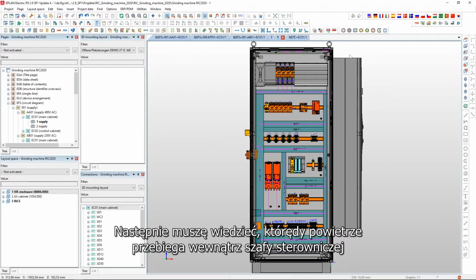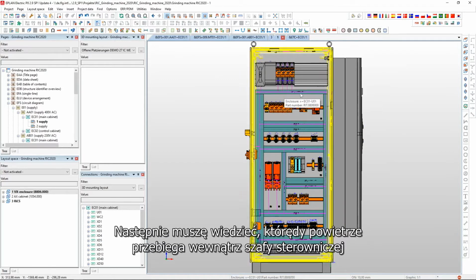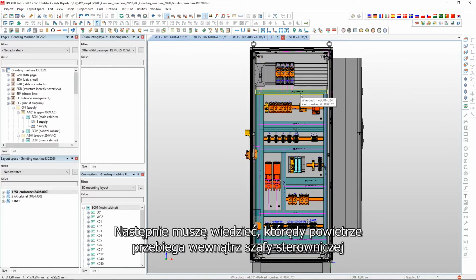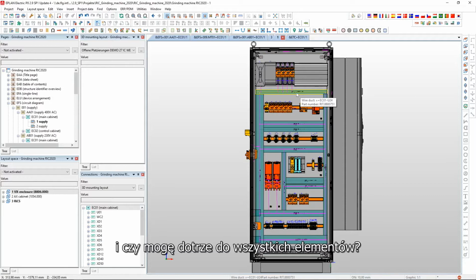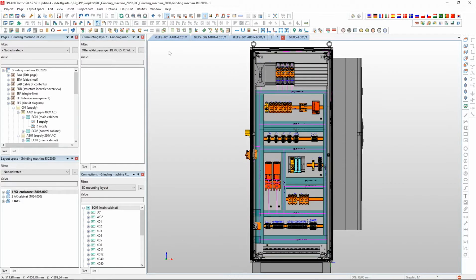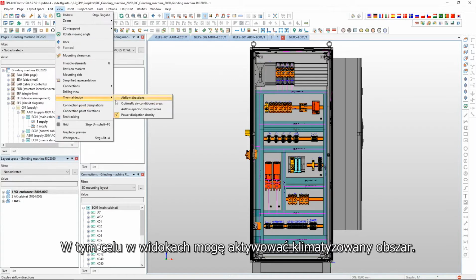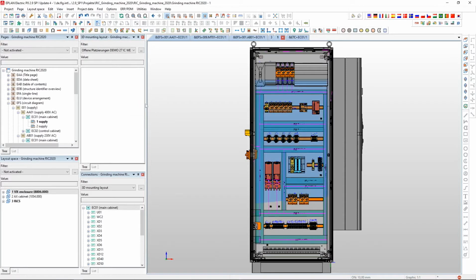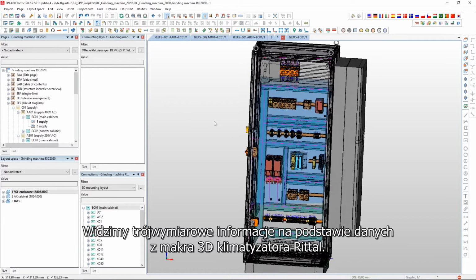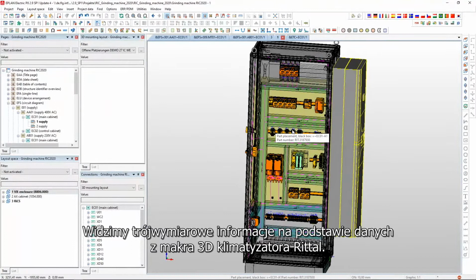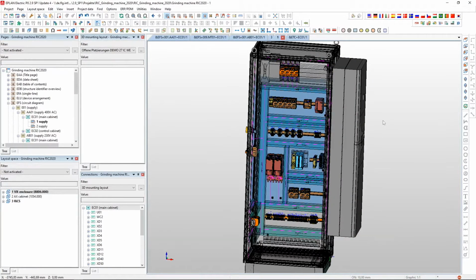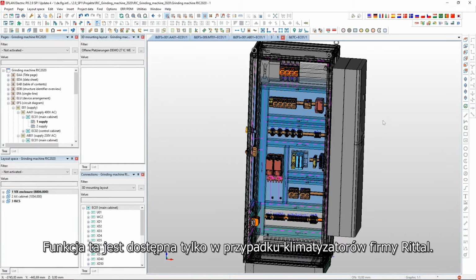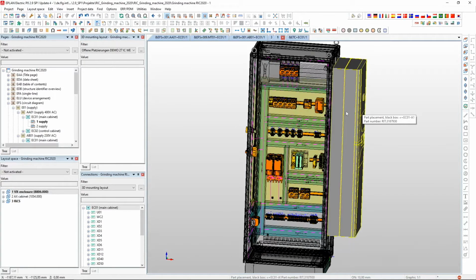The next question is, I have to know where the airflow is inside the enclosure, to know if I can reach all components. We can activate the conditioned area in the views, and here we see 3D information depending on data from the 3D macro of a Rittal cooling unit, because this is only possible with a Rittal cooling unit.